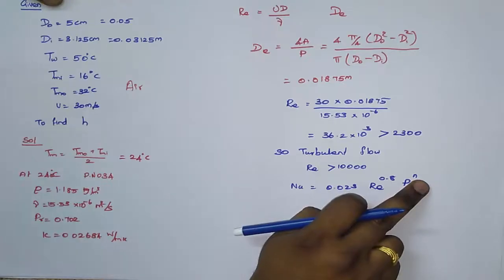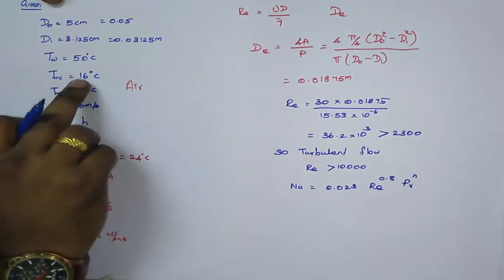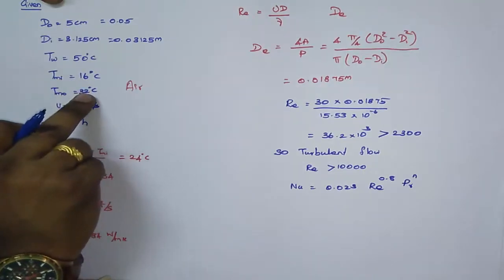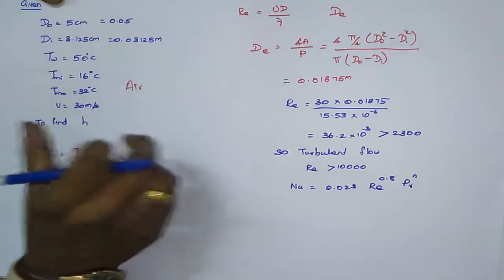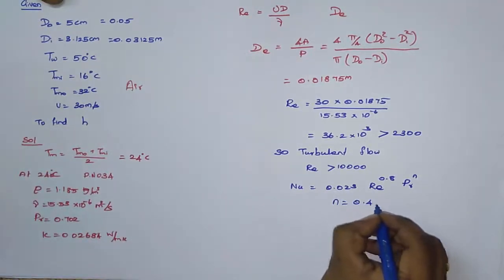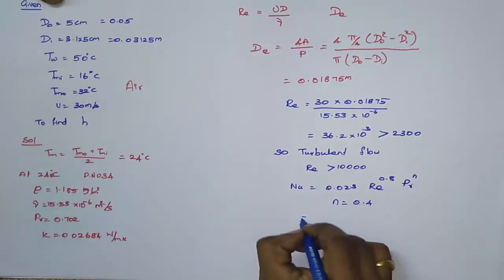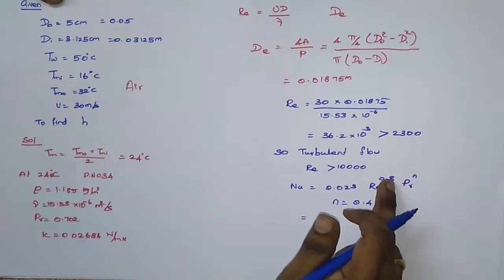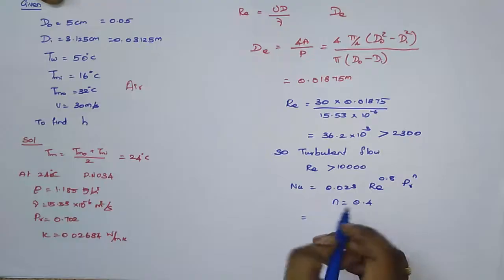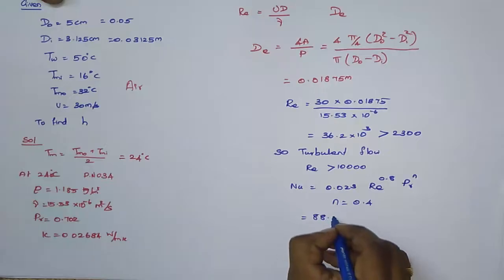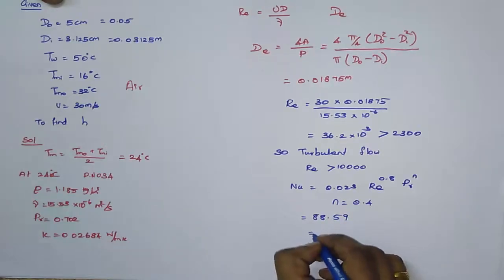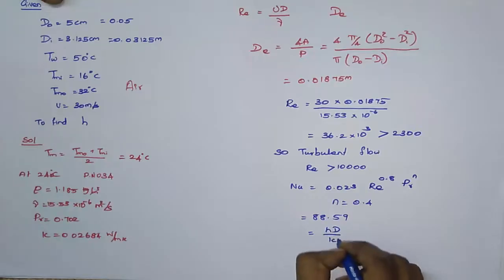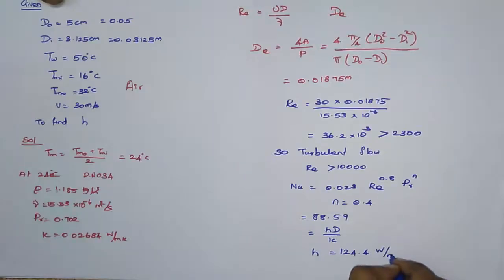For turbulent flow, use the Dittus-Boelter equation: Nu = 0.023 × Re^0.8 × Pr^n. Since inlet temperature (16°C) is less than outlet temperature (32°C), this is a heating process, so n = 0.4. Substituting all values gives Nu = 88.59. From Nu = hD/k, solving for h gives h = 124.4 W/m²·K.